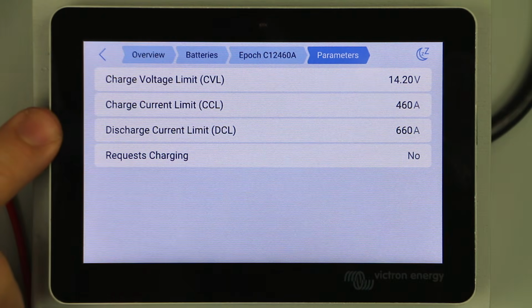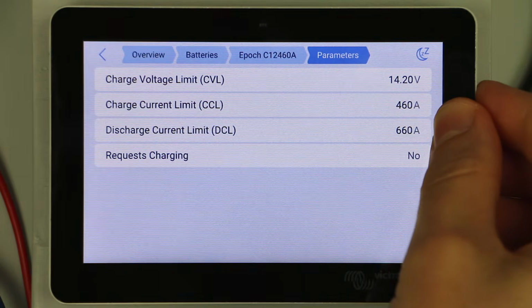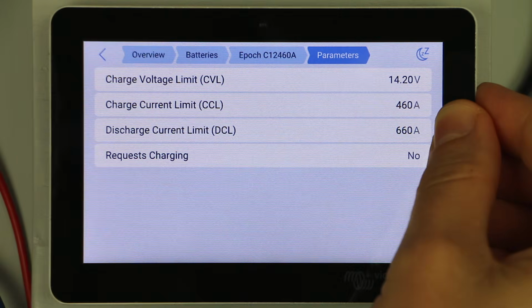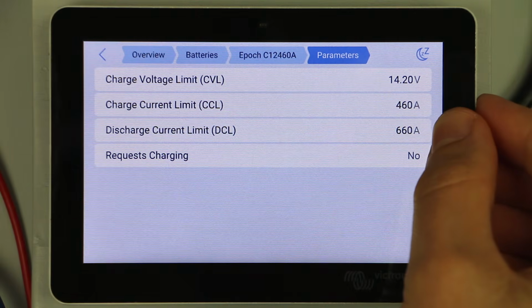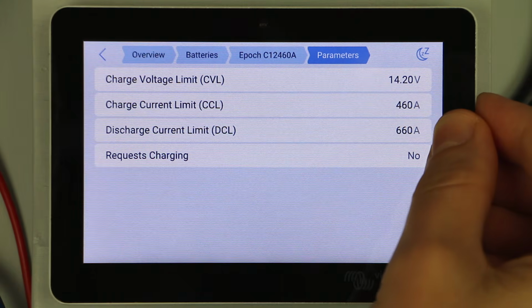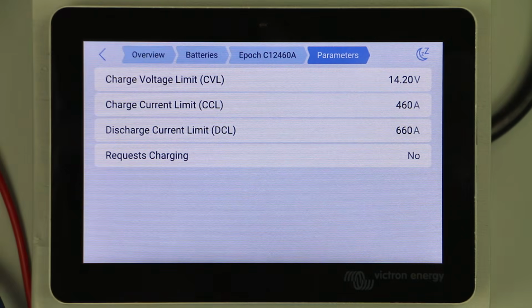Next up, we have our discharge current limit. Again, this number is not going to drop very often. It's 330 amps per battery for the 12 volt model. And if you run the battery bank down close to zero and there's hardly any power left in the batteries, this number may drop. Again, that's the batteries telling the overall system what they're able to put out based on where they are in the charge cycle.